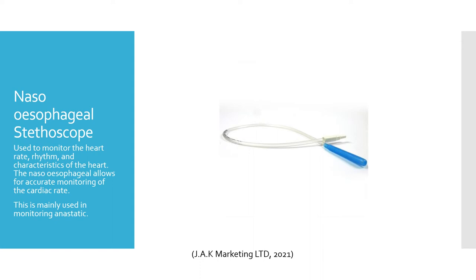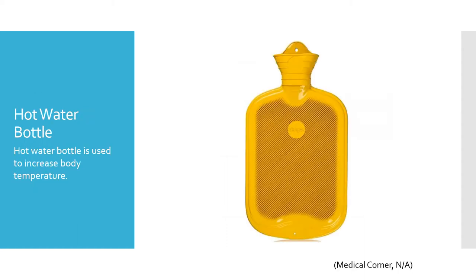Although nasal esophageal stethoscopes can be safe when used properly, they may cause reflux esophagitis. Esophageal stethoscope placement should be done carefully so as not to accidentally pass through the trachea. While the tube is soft and flexible, care should be taken when inserting it into the fragile area of the esophagus. The presence of a heartbeat does not guarantee circulation, so the esophageal stethoscope must be used alongside other cardiovascular monitoring systems.